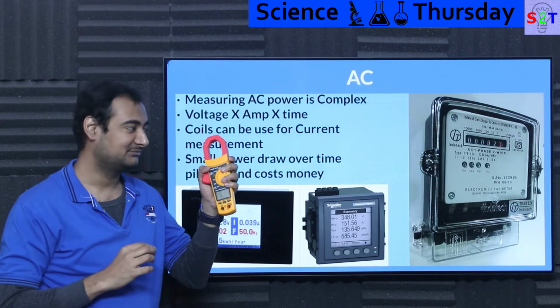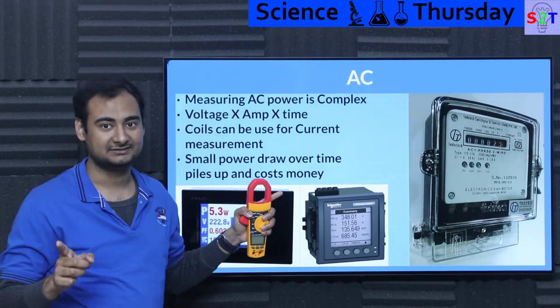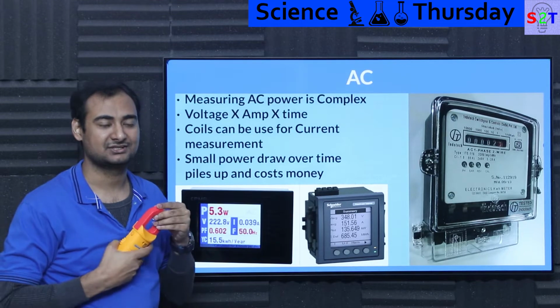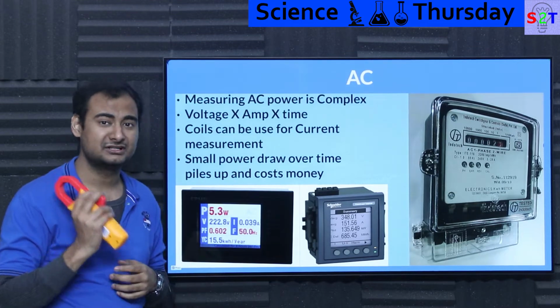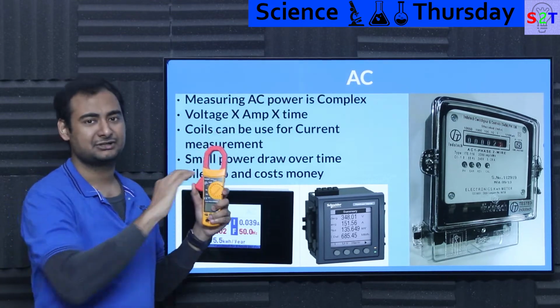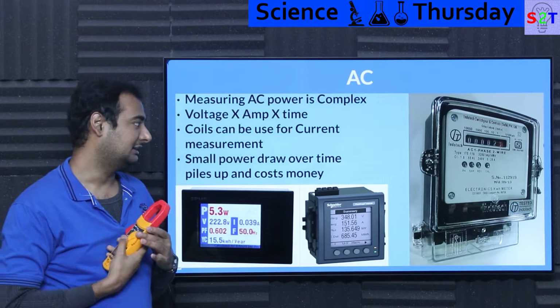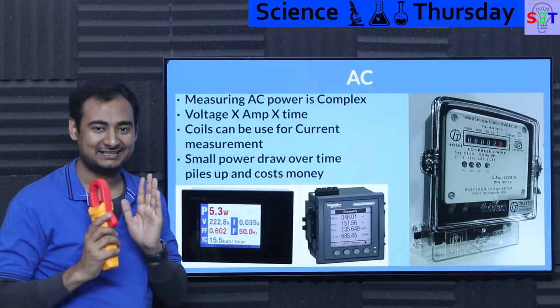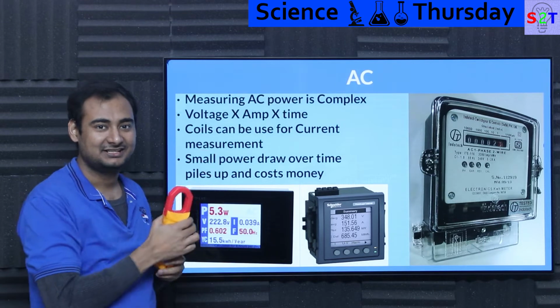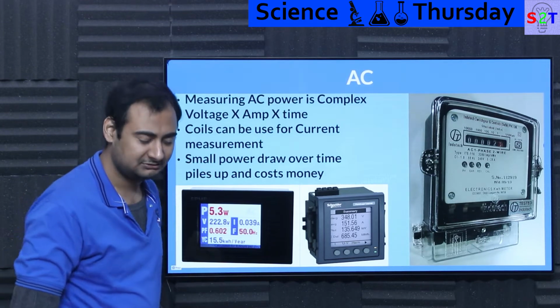This means I can measure the power draw of a big building, as long as the voltage isn't too dangerous to be around, say 400 to 600 volts, this can clamp on and read it properly, no issue. But there's still a limitation, don't try this on a substation, it'll go poof with you probably.